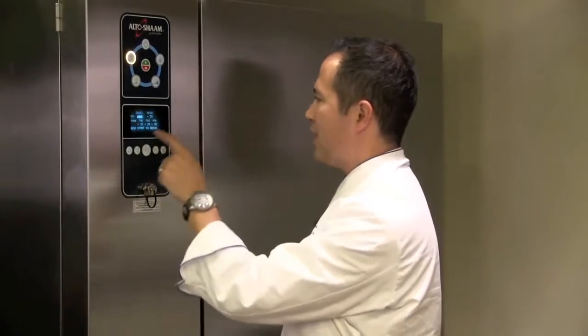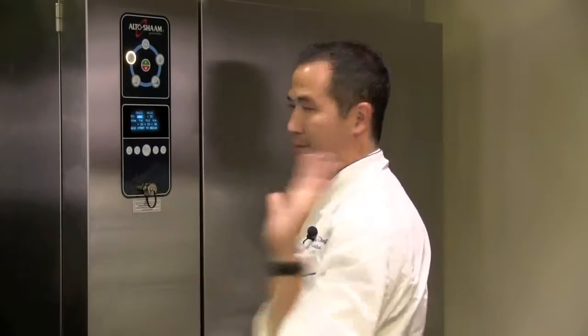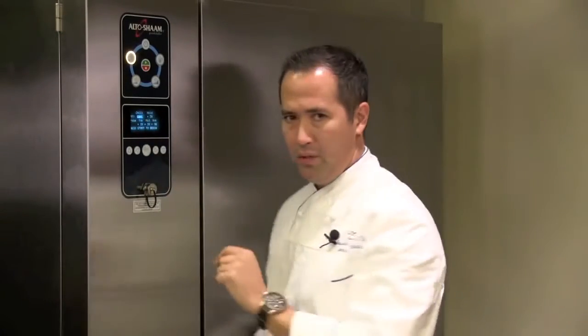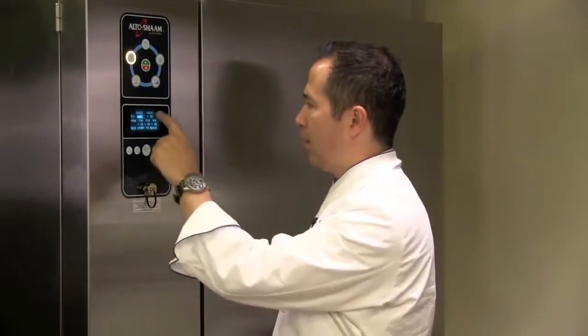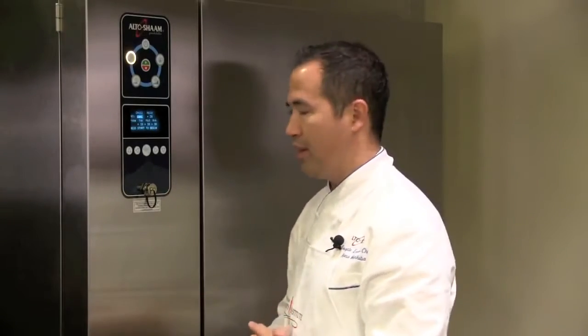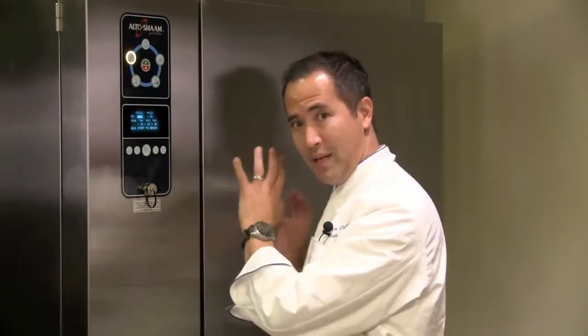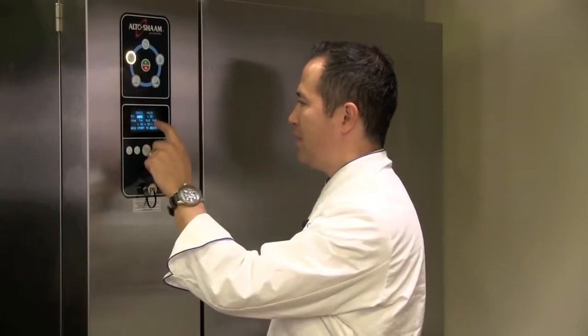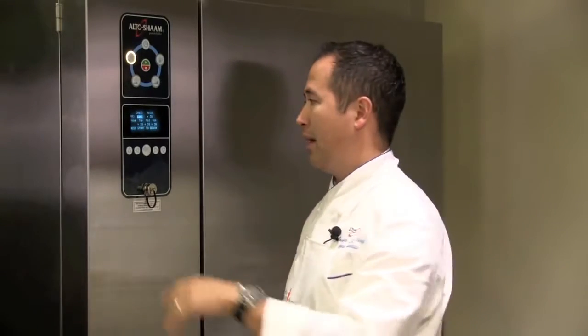Now on this screen it shows 5 numbers: the chill temperature, which is the temperature of the chiller cavity when we put the food in; the hold temperature, which is what the chiller will rise to after chilling is done—that's the temperature inside the chiller when you come in the morning to take the food out; and the 3 temperatures on the bottom, which we generally leave the same, are the cutoff temperatures for the 3 individual probes.